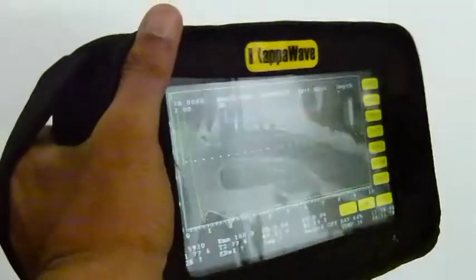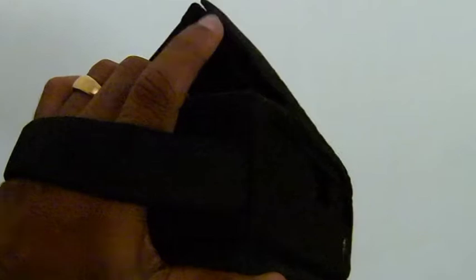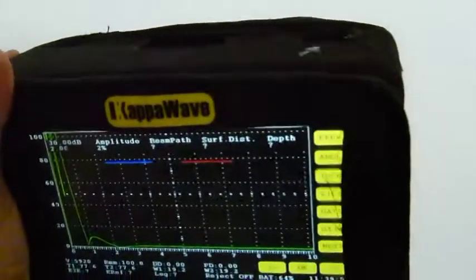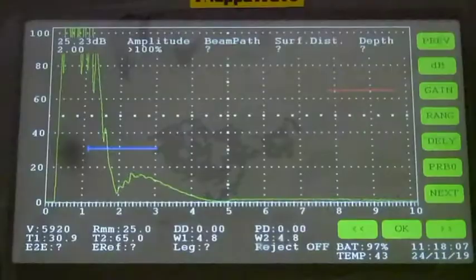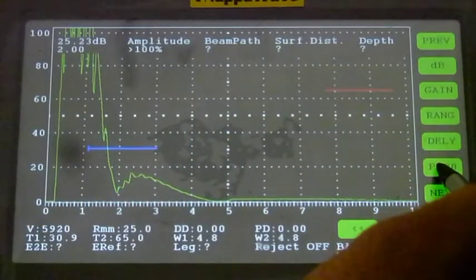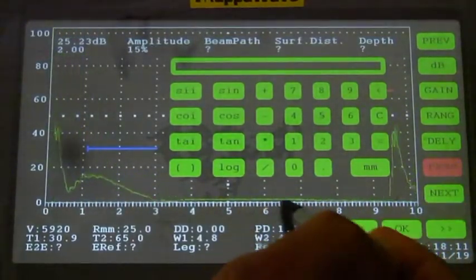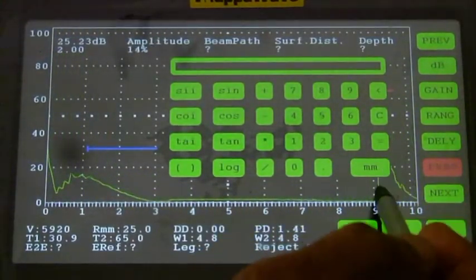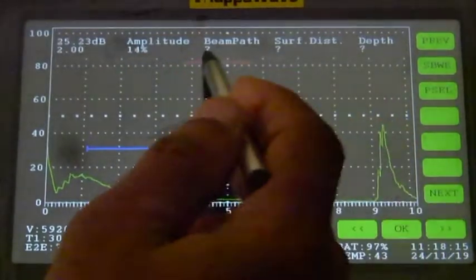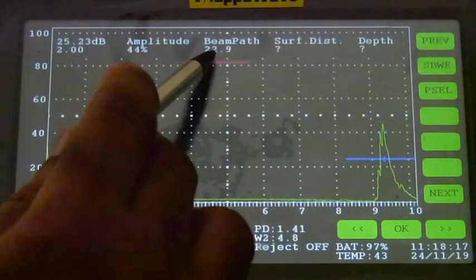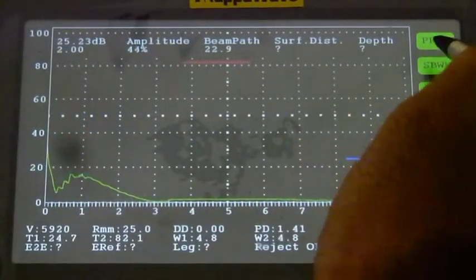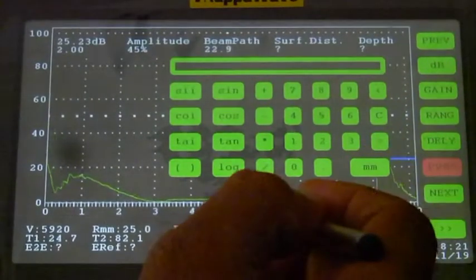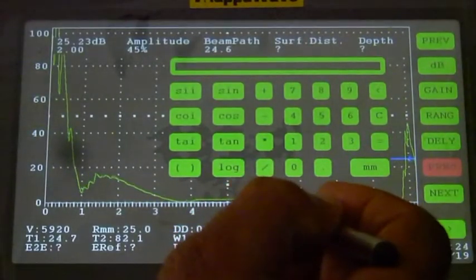K8 is a very lightweight instrument that may be easily carried anywhere. Calibration of the instrument becomes fairly easy. With a given thickness of 25 millimeter, using a probe zero function, this may be correctly set to read 25 millimeter distance.